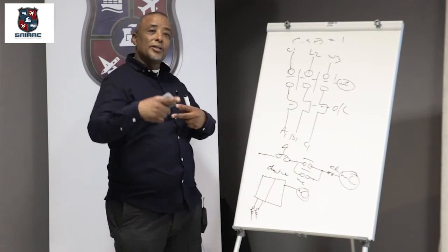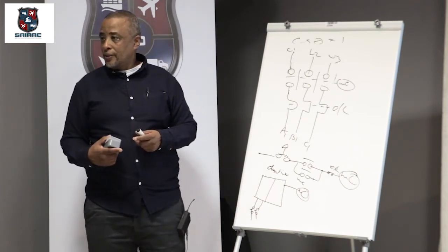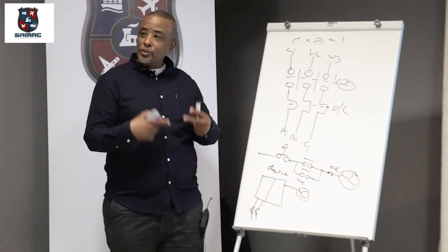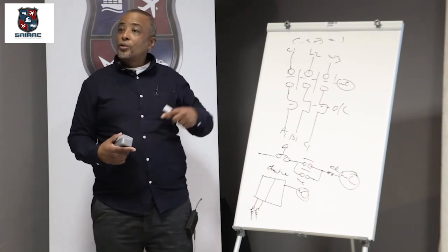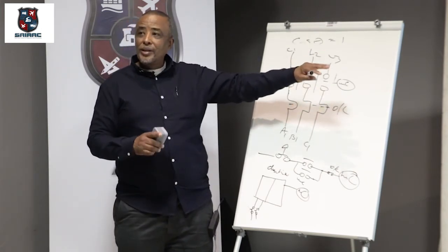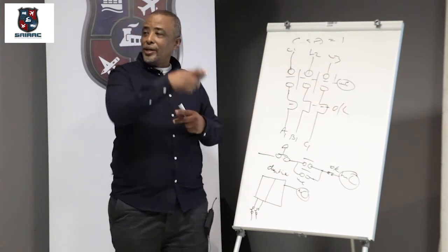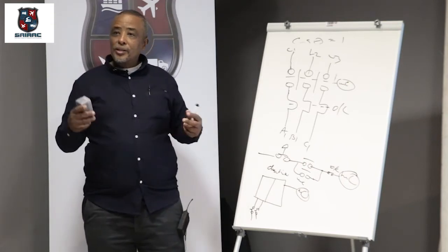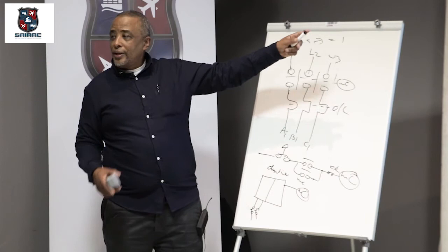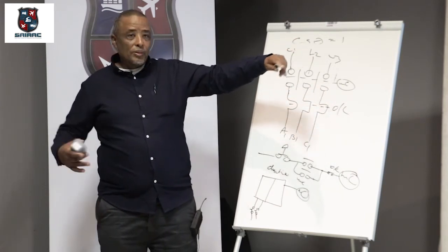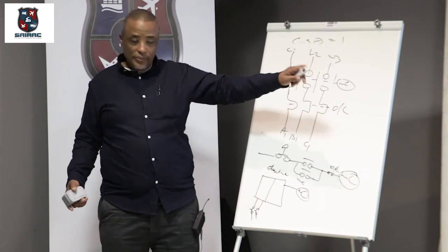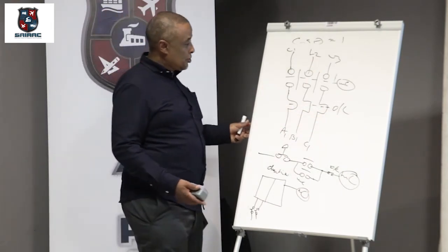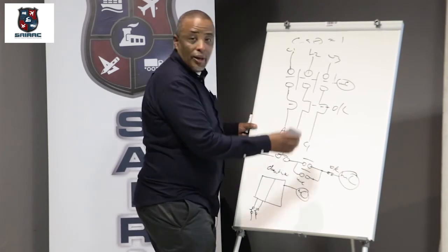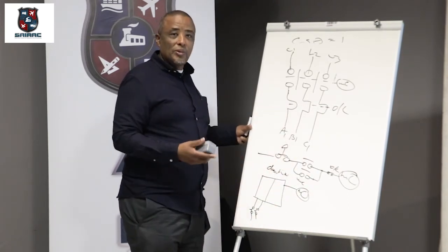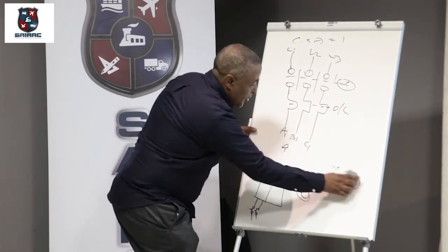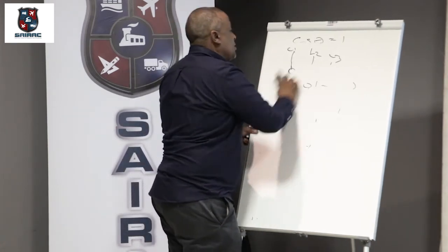The phase shift there would be 90 degrees. You need to create a phase shift to be able to have a rotating magnetic field. Be clear with that. So in the case of three-phase AC, we don't need anything else. The windings are there. We don't need to add capacitors to create phase shifts. There is an angular displacement of 120 electrical degrees apart, so it is self-starting. Okay, are we happy with the direct online starter? Simple, eh? Can we go on to the forward-reverse starter?